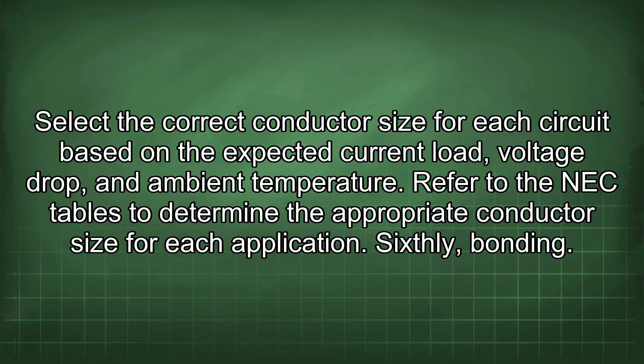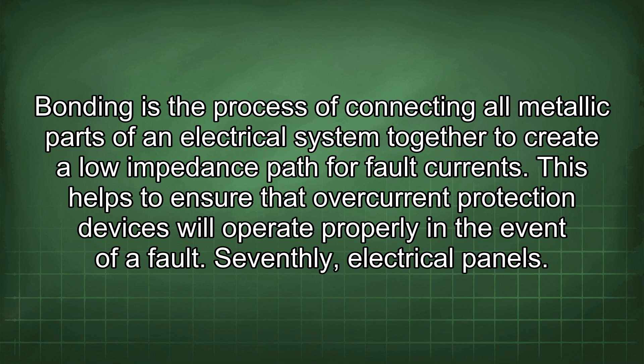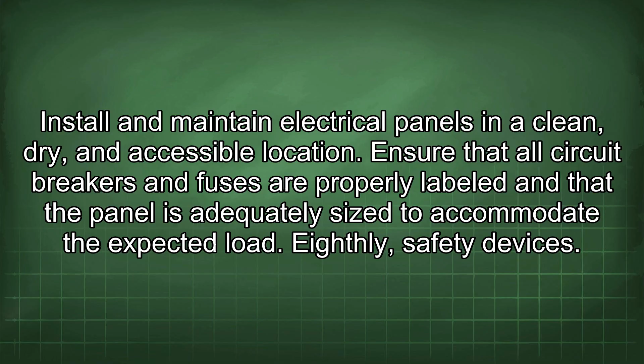Sixthly, bonding. Bonding is the process of connecting all metallic parts of an electrical system together to create a low impedance path for fault current. This helps to ensure that overcurrent protection devices will operate properly in the event of a fault. Seventhly, electrical panels. Install and maintain electrical panels in a clean, dry, and accessible location. Ensure that all circuit breakers and fuses are properly labeled and that the panel is adequately sized to accommodate the expected load. Eighthly, safety devices.